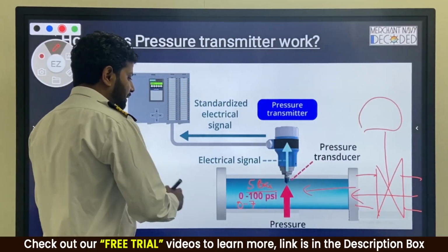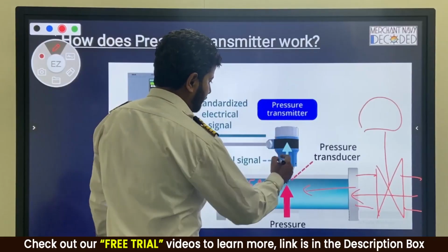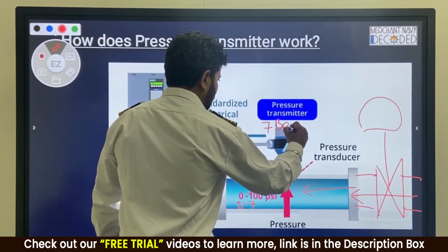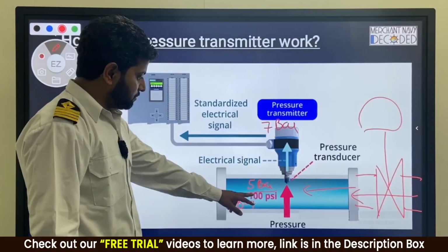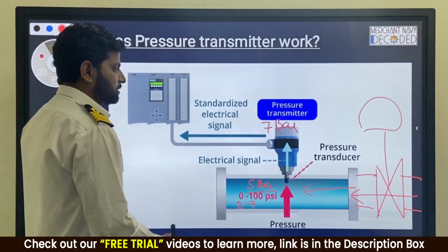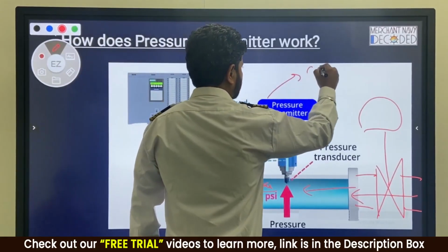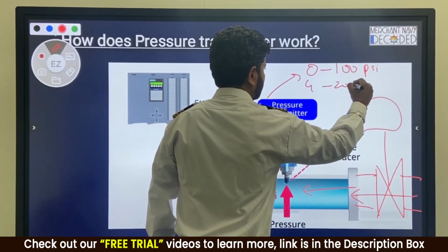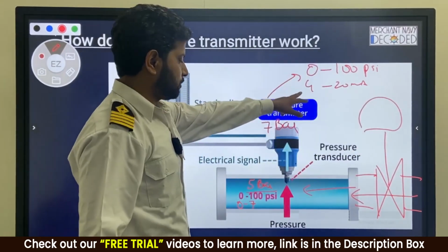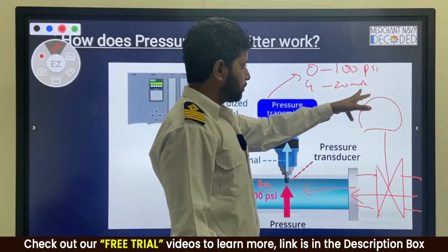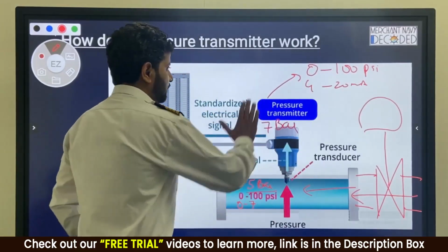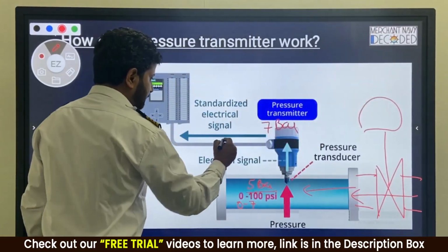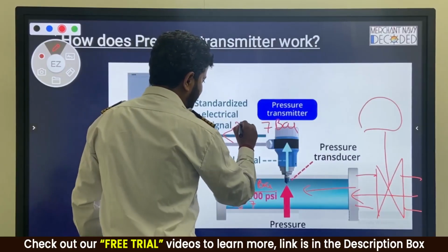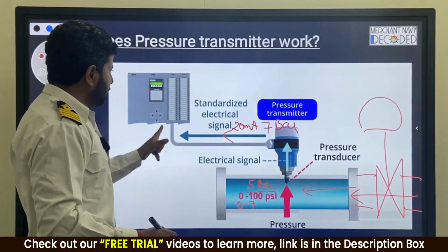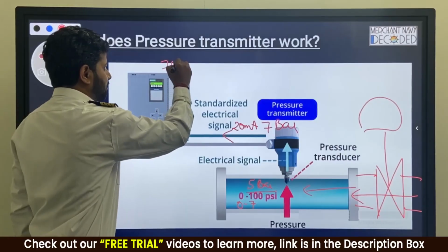Copy it guys. So what happens is, say the pressure is 7 bar. Right now the pressure is 7 bar. So 7 bar means this is the maximum value, 0 to 100 psi. If the pressure transmitter is calibrated at 0 to 100 psi as 4 to 20 milliamps, that means if it is 0 bar then 4 milliamps, 100 psi that is 7 bar then 20 milliamps. See, it is calibrated like this. So right now the current that it will show over here will be how much? 20 milliamps.